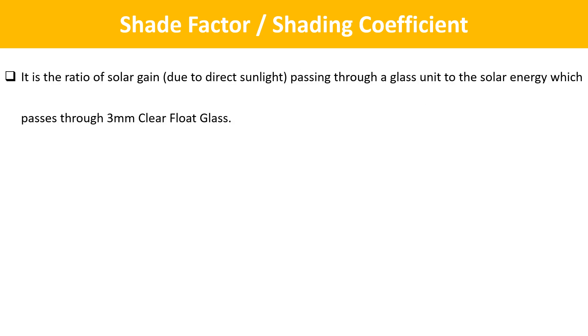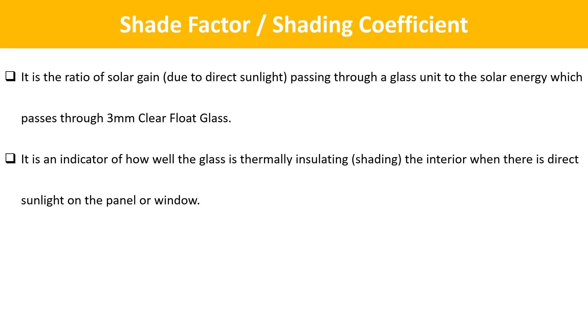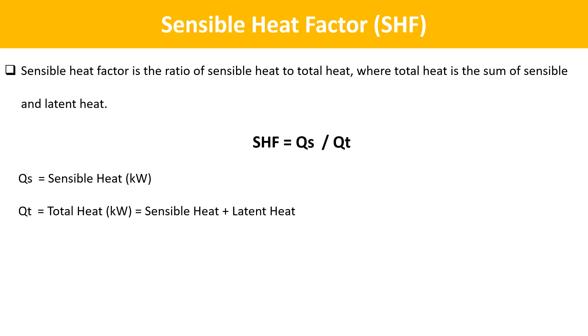The next term is Shading Coefficient. It is the ratio of solar gain due to direct sunlight passing through a glass unit to the solar energy which passes through 3 mm clear float glass. It is an indicator of how well the glass is thermally insulating the interior when there is direct sunlight on the panel or window. The next term is Sensible Heat Factor. Sensible heat factor is the ratio of sensible heat to total heat, where total heat is the sum of sensible and latent heat.